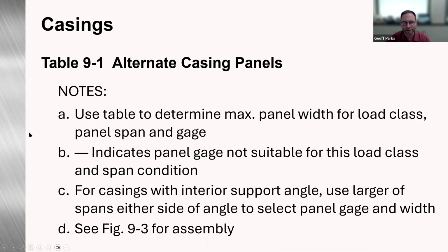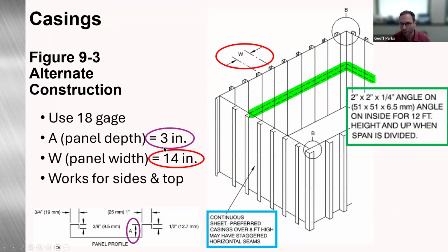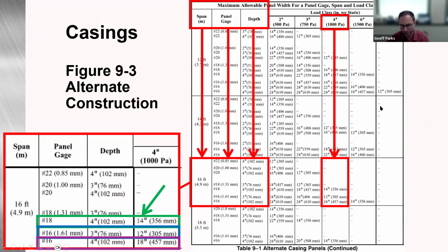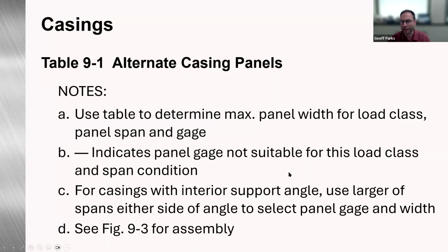Table 9-1 is the table that gives you all the gauging, the depth and the panel widths. Some notes from that table: you would use the table to determine the maximum panel width for the load class, panel span, and gauge. If there was a dash mark within that table, I'll go back real fast, see all these dash marks here, that indicates that the panel gauge is not suitable for the load class or the span condition. For casings with interior support angle, if you're spanning that 12 foot, you would use the larger of the spans on either side of the angle to select the panel gauge and width. And of course, figure 9-3 is your assembly figure, giving you all the nitty-gritty details to actually fabricate and assemble it.